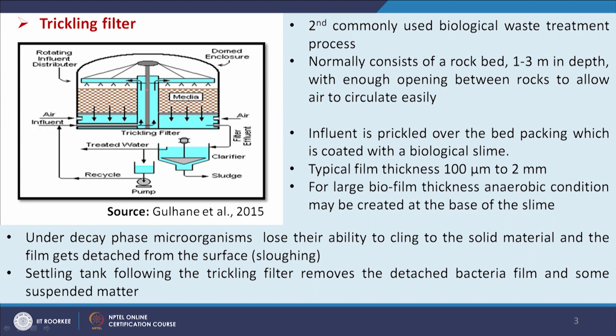After degradation of the organic compounds, the water is collected and then goes to the clarifier, and then sludge and water go for further tertiary treatment. This is the second commonly used biological waste treatment process, normally consisting of a rock bed 1 to 3 meters in depth with enough opening between rocks to allow air to circulate. Influent is trickled over the bed packing, which is coated with a biological slime, and typical film thickness is 100 micrometers to 2 millimeters.